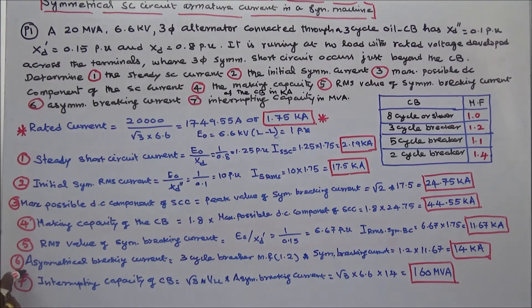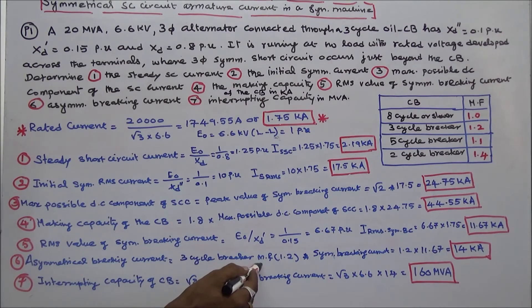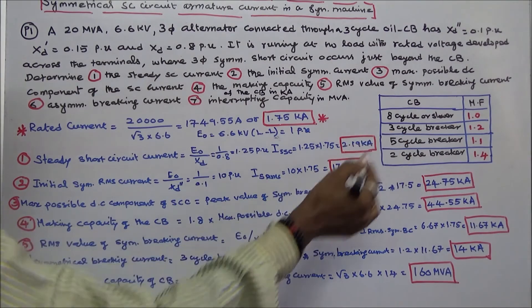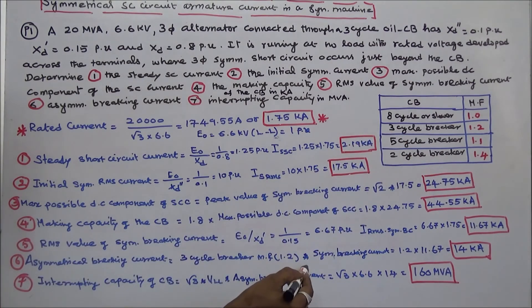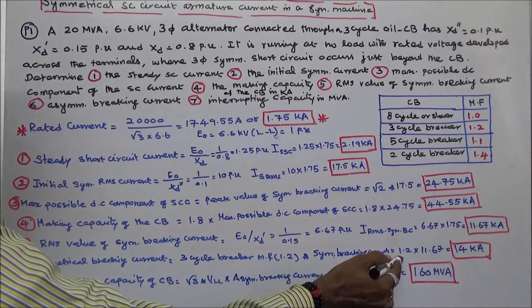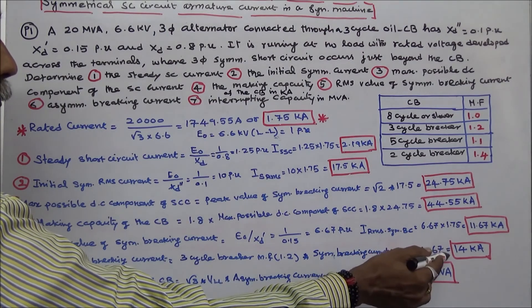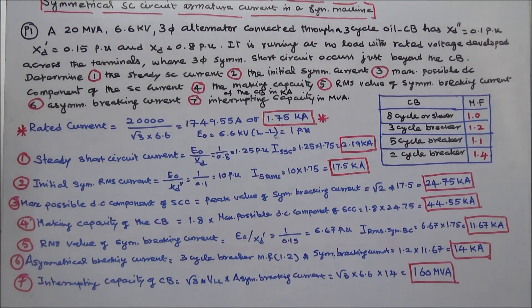Sixth is the asymmetrical breaking current. That equals the 3-cycle breaker multiplication factor of 1.2 multiplied by the symmetrical breaking current. 1.2 into 11.67 equals 14 kA.